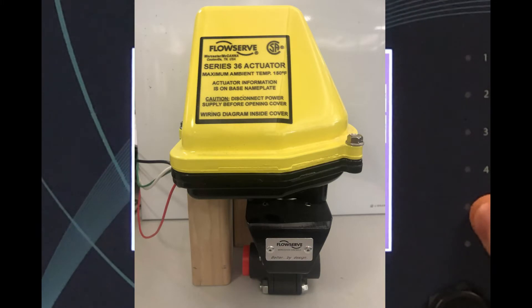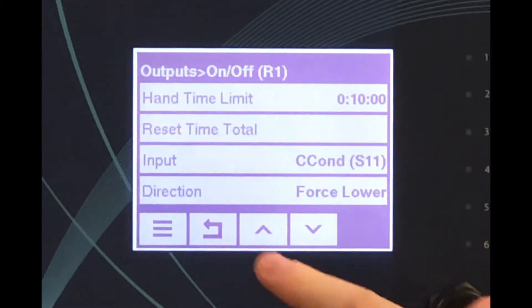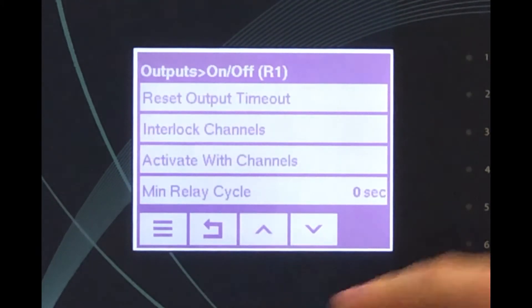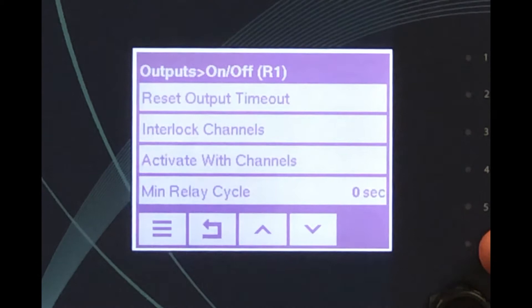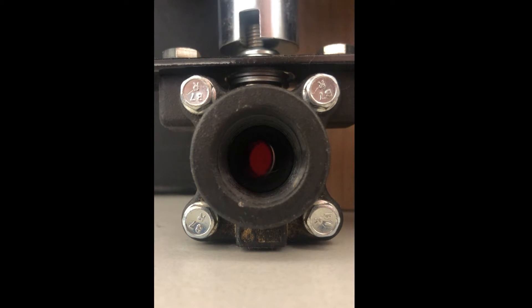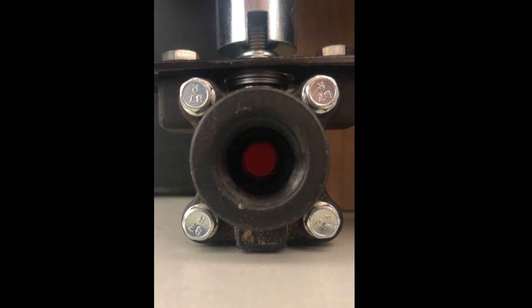When using a motorized ball valve for the blowdown valve, it is also important to set a minimum relay cycle that is longer than the amount of time it takes for the ball valve to move from its fully open position to its fully closed position and vice versa. If the relay is able to change its state before the valve is finished actuating, the valve can get stuck in a partially open or closed position and not function properly.